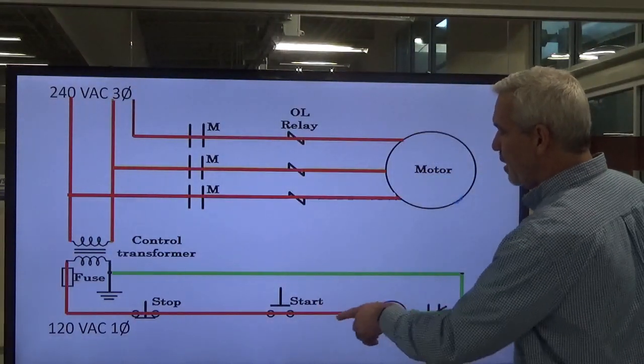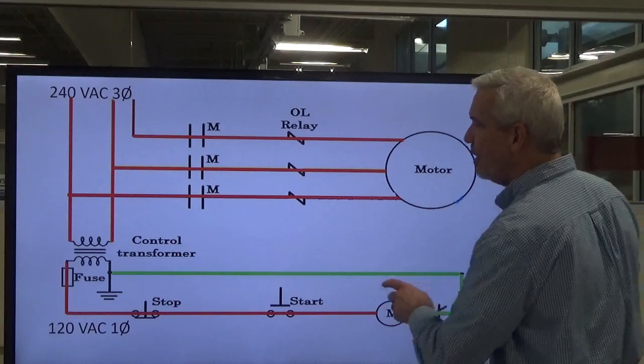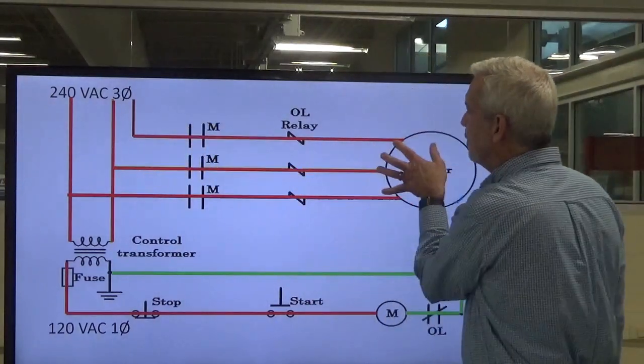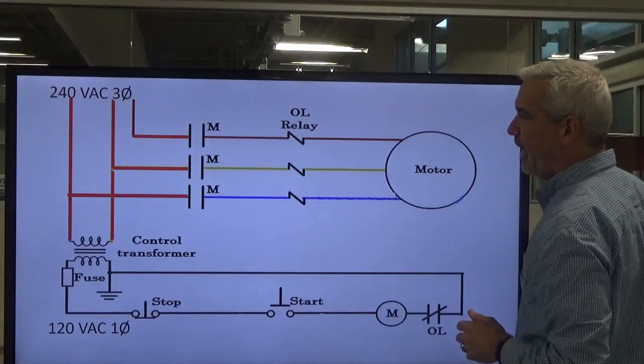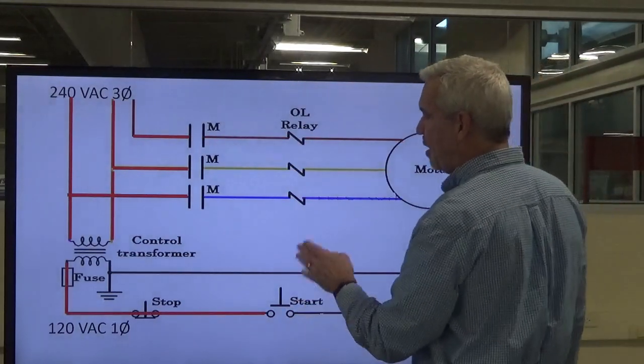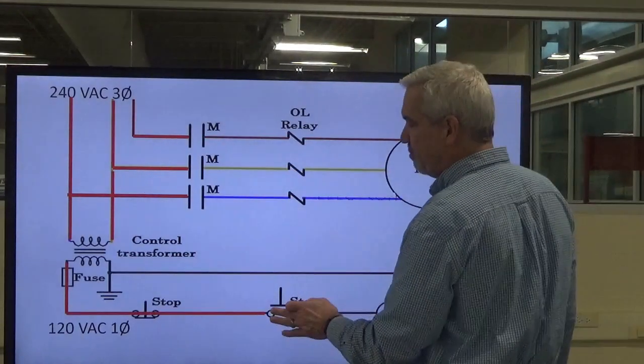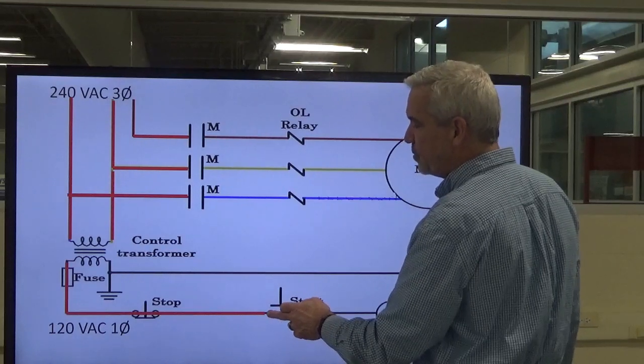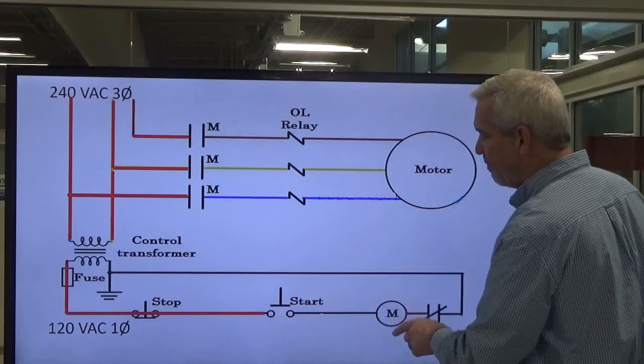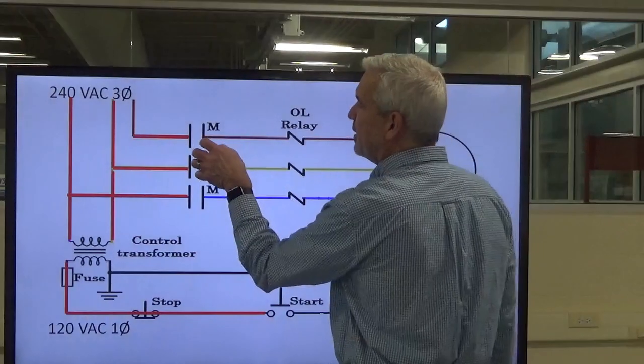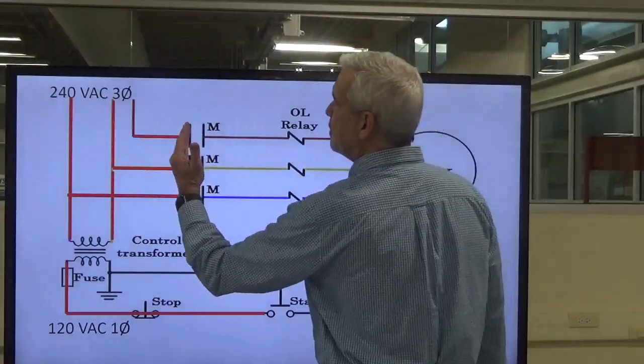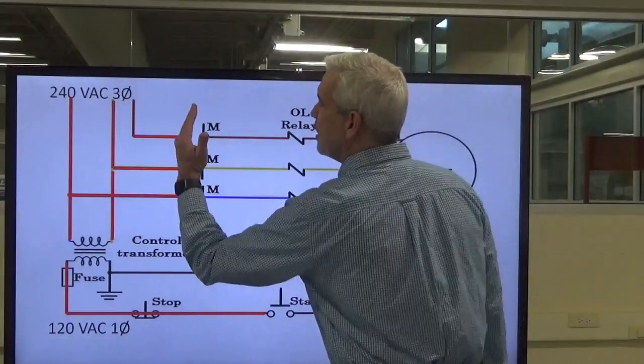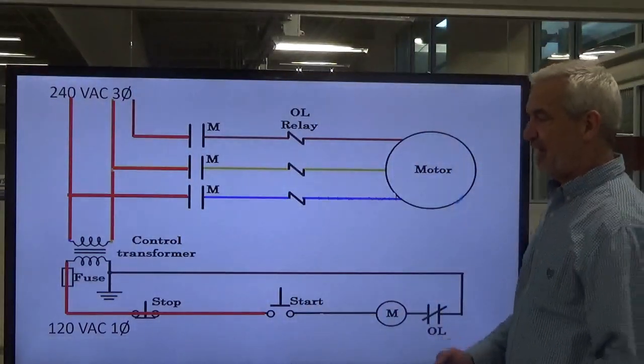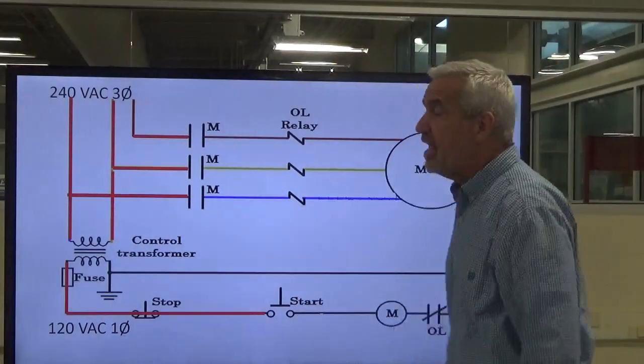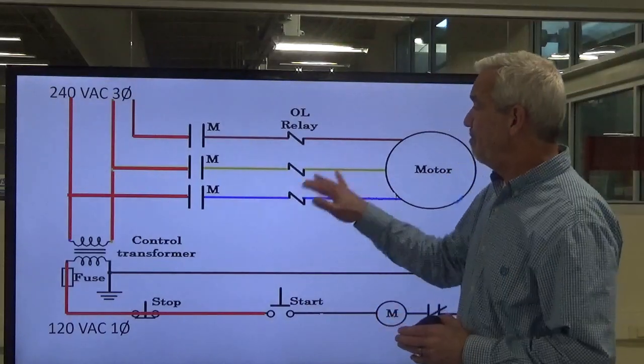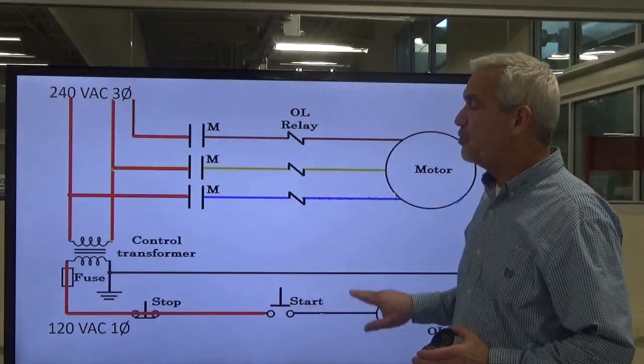We're running along here. We've energized the motor starter coil. It has pulled these contacts closed. We are running our motor, and then we let go of the start button, and all of a sudden the secondary voltage stops here. We no longer have an energized coil. These contacts pop back open, and our voltage is cut off from our motor, and it's just sitting there waiting on the contacts for the next time for us to push the start button. Okay, and that's how we control the motor with our control circuit.